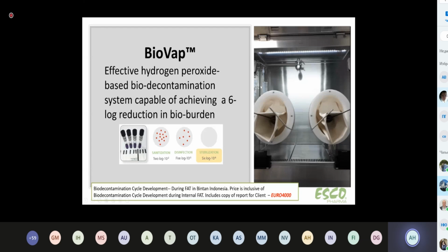So all of this here will be tested. We have to know how long we need to gas the machine. And the length of the gassing is a frequently asked question by the customer. So the biodecon process is not like few minutes you wipe, everything is okay. Sometimes it takes 45 minutes. Sometimes it can be as long as 2 hours, depending on what kind of materials that you use inside the isolator. If you have more items, you have more load, then you have more time.